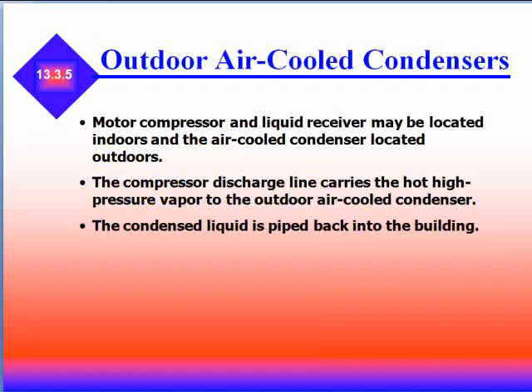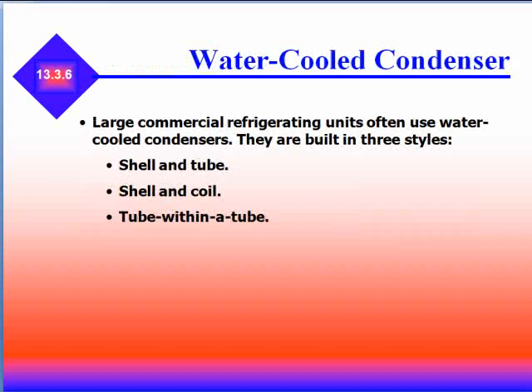Motor compressors and liquid receivers can be located inside, with the air-cooled condenser located outside. The compressor discharge line carries the hot, high-pressure vapor to the outdoor air-cooled condenser, and the condensed liquid is piped back into the building. Large commercial units can also use water-cooled condensers, which are built in three styles: shell and tube, shell and coil, and tube within tube.